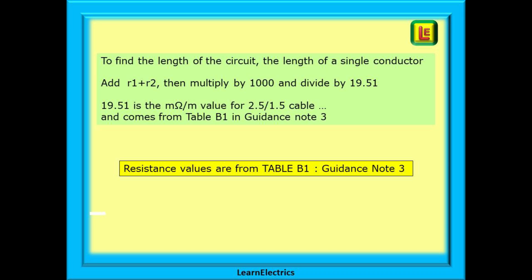And to find the length of the circuit, the length of a single conductor, add little R1 plus little R2, then multiply by 1000 and divide by 19.51. 19.51 is the milli-ohms per metre value for 2.5 1.5 cable, and this comes from table B1 in Guidance Note 3.